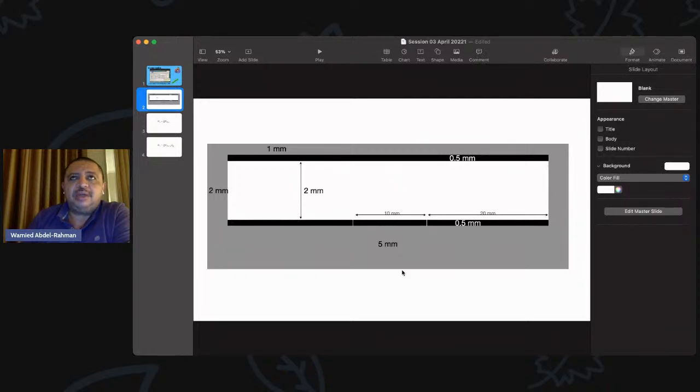And then we have, obviously this is cylindrical symmetry. So we have the polarizing electrode here, with a thickness of 0.5 millimeter, made out of graphite. There is an entrance window of 1 millimeter for the chamber. So all of this, the gray material, is PMMA. This is graphite or carbon, thickness of 0.5 millimeters.